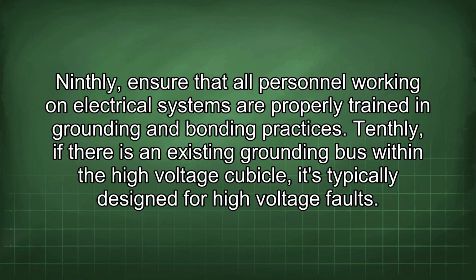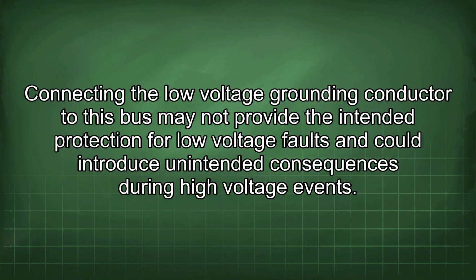Tenthly, if there is an existing grounding bus within the high voltage cubicle, it's typically designed for high voltage faults. Connecting the low voltage grounding conductor to this bus may not provide the intended protection for low voltage faults and could introduce unintended consequences during high voltage events.